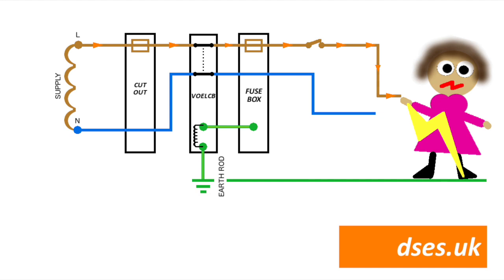Once again Doris is now part of the earth fault loop path for this circuit. So what's our voltage operated earth leakage circuit breaker going to do about it? Well, absolutely nothing. Not a single microamp of the fault current is passing through its coil. Poor Doris is toast and her smoking corpse will come to rest on her half-mowed lawn.